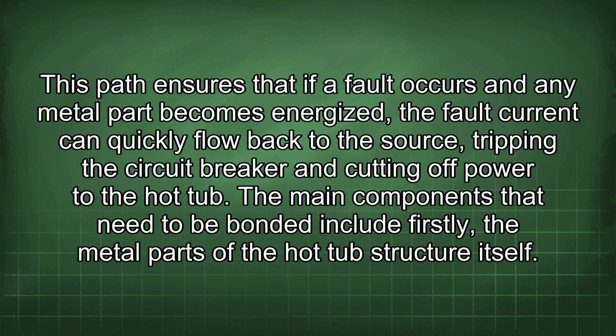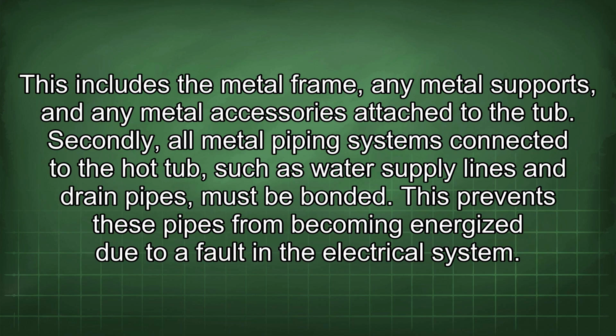The main components that need to be bonded include, firstly, the metal parts of the hot tub structure itself. This includes the metal frame, any metal supports, and any metal accessories attached to the tub. Secondly, all metal piping systems connected to the hot tub, such as water supply lines and drain pipes, must be bonded. This prevents these pipes from becoming energized due to a fault in the electrical system.